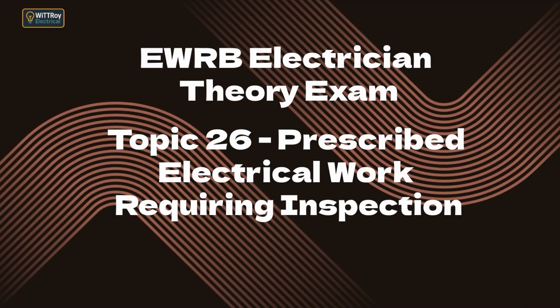Work requiring inspection under Regulation 70 includes: work on mains that involves the main connection, earth electrode, or earthing system; work where the main earthing or bonding conductors have been altered or replaced; work on main switchboards affecting earthing or main links; installation work in hazardous areas; medical locations classified as cardiac protected; and any work listed in Schedule 1 that is classed as high-risk prescribed electrical work. The key point: if the safety of the main system, the earthing system, or the supply protection is affected, an inspection is required.